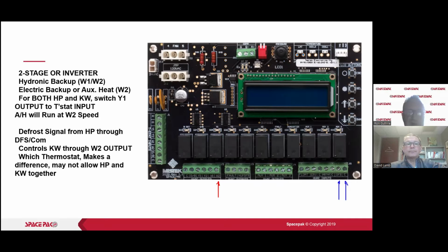Yeah, the 24 volts is coming through Y1. There are like 4 wires, and I've seen this on a couple of heat pumps. There are only like 4 wires. There's not an R going down to, you know, an R, which is 24 volts. But we have 24 volts already going to the outdoor unit. We've got a Y. We've got an L or B if we need that at that particular time to tell the reversing valve when to work in heating or cooling. We've got a common, and we've got a W, which is going to relate to heating. In mine, that's really all I have, and that's all I've seen in the field. I don't know if you need an R because you're getting 24 volts through Y.